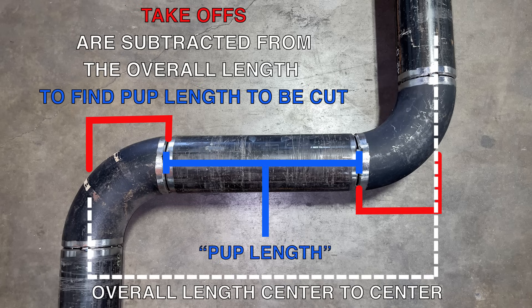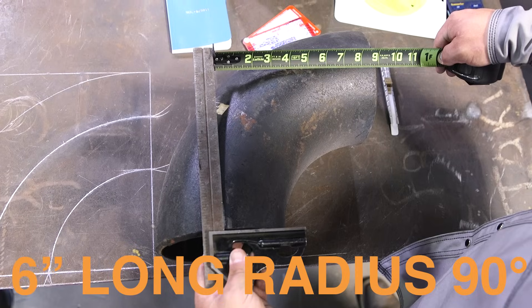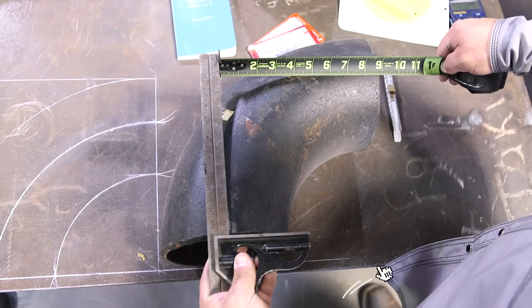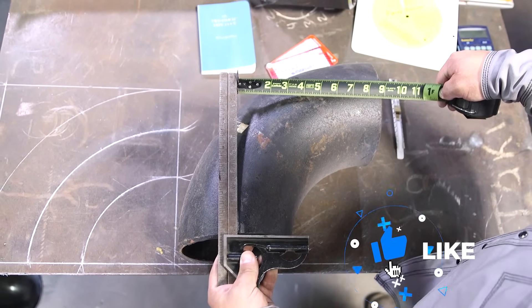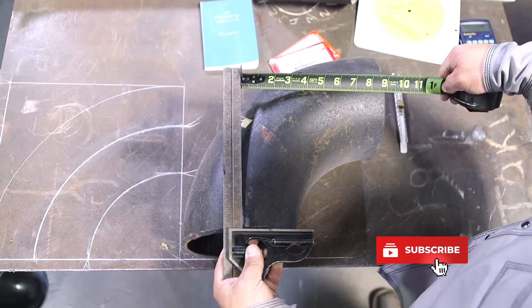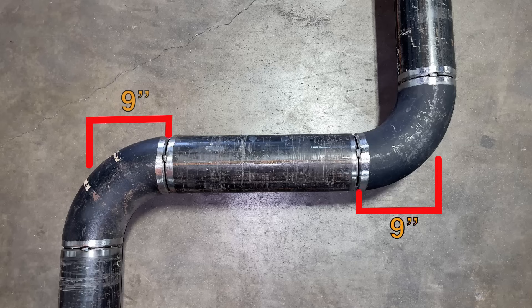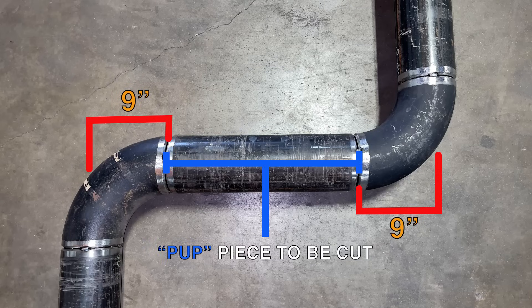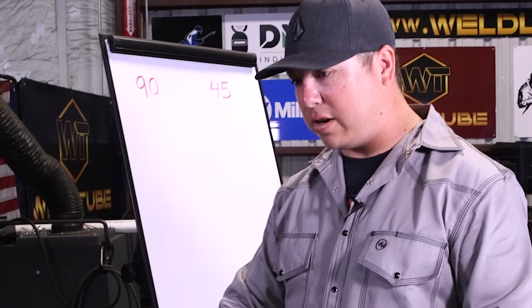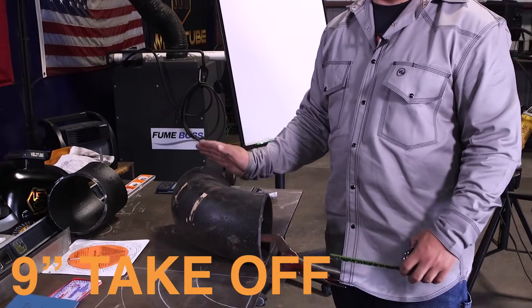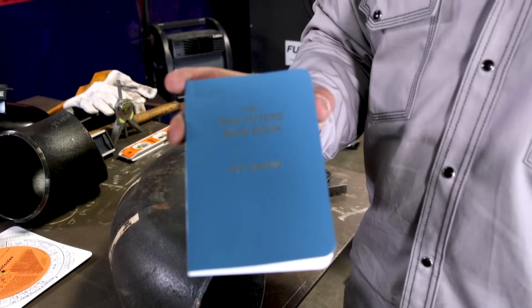All right guys, so I got a 6 inch long radius 90 here and I'm going to explain to you guys what the actual takeoff is when we're accounting for our measuring here. So the takeoff of this is the section of pipe that we are going to remove in order to account for the distance this 90 is. So on this particular case, a 6 inch 90 here, it's going to be 9 inches. And how do we find this information?